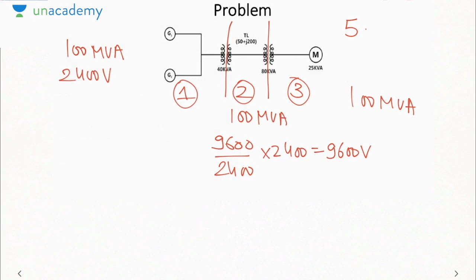The transformation ratio for T2 is 10 by 5 kV. So it will be 5 by 10. Primary voltage is 9600 because the secondary voltage of T1 will be the primary voltage of T2. So it is 4800 volt. So now if you see, the base voltage can be different from the rated because the rated secondary voltage of T2 is 5 kilovolt, whereas here the base is 4800 volt. So do not directly go on assuming the rated voltage as the base voltage, it can be different. Now we have bases for all the sections.